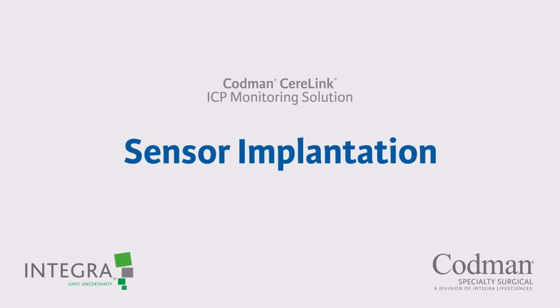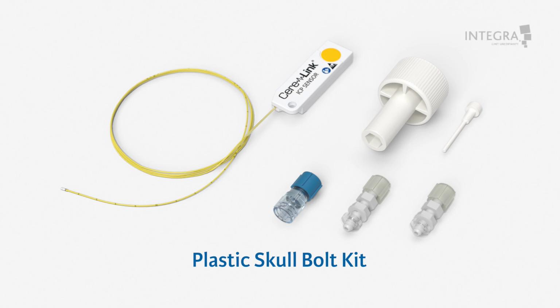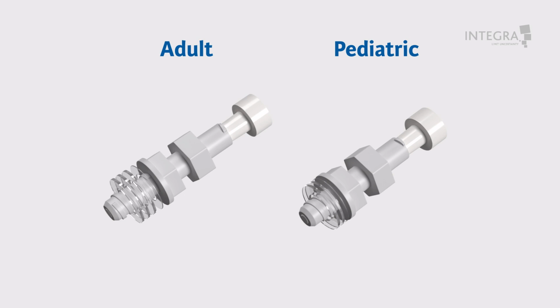3. Sensor implantation. The CereLink ICP sensor plastic skull bolt kit consists of an intracranial pressure ICP sensor with a Tuohy-Borst adapter mounted on the catheter, one adult and one pediatric skull bolt with spacing washers, and a disposable ICP screw handle for facilitating bolt removal. Select the adult or pediatric bolt. If desired, adjust the seating depth of the plastic bolt using the spacing washers provided. Position spacing washers prior to insertion of the bolt.